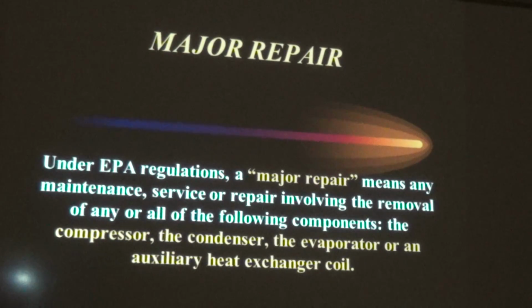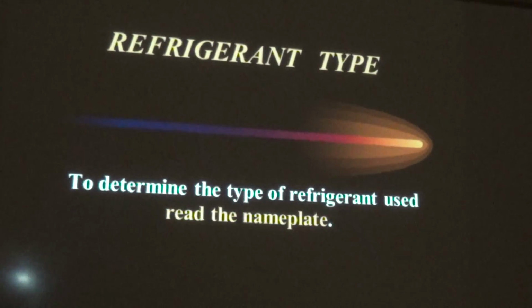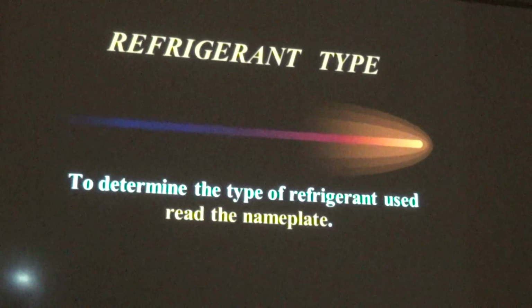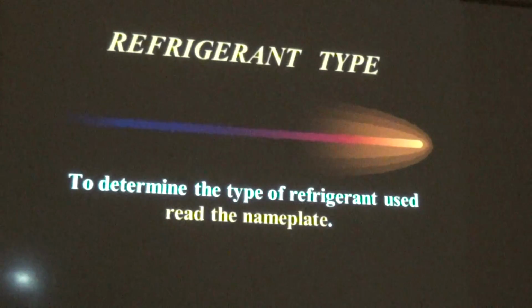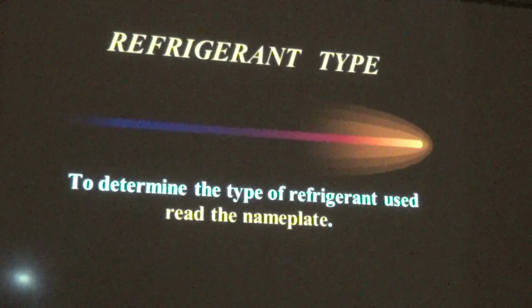Major repair. Major repair test question type 1, type 2, type 3. If you remove any of these components, the compressor, the condenser, the evaporator, or an auxiliary heat exchanger coil, those equal major repair. It's the same for type 1, type 2, type 3. Same question. To determine the kind of refrigerant, I recommend reading the nameplate. That sounds pretty self-explanatory.